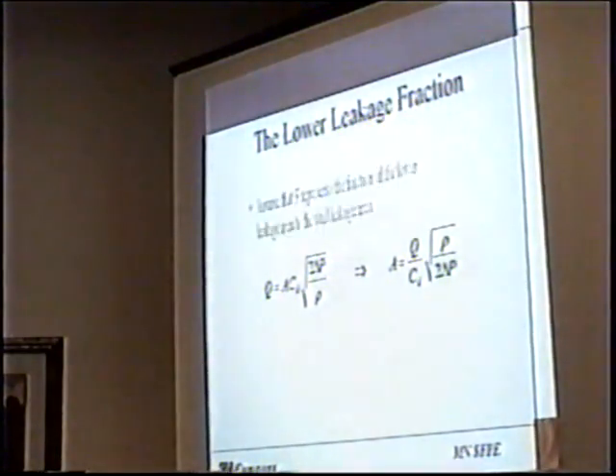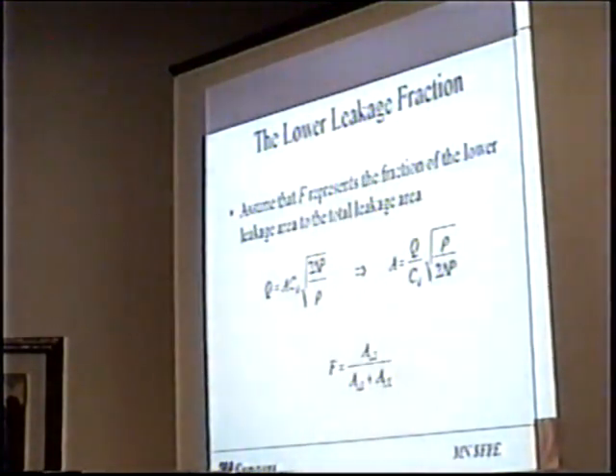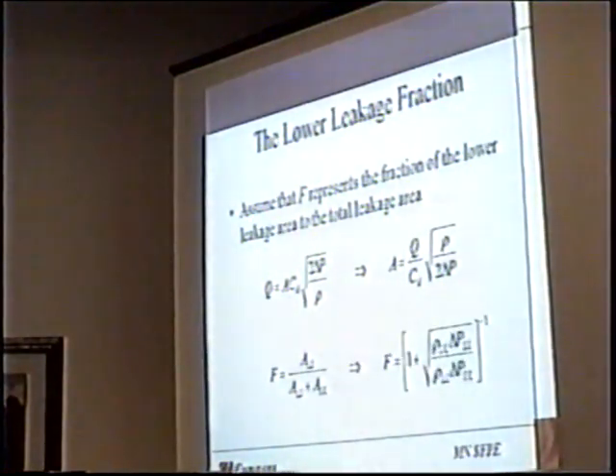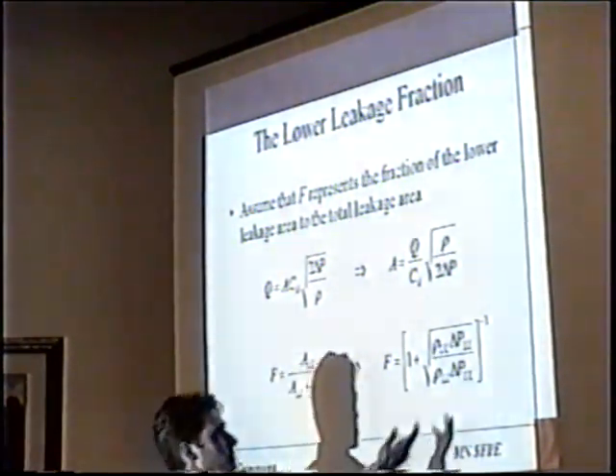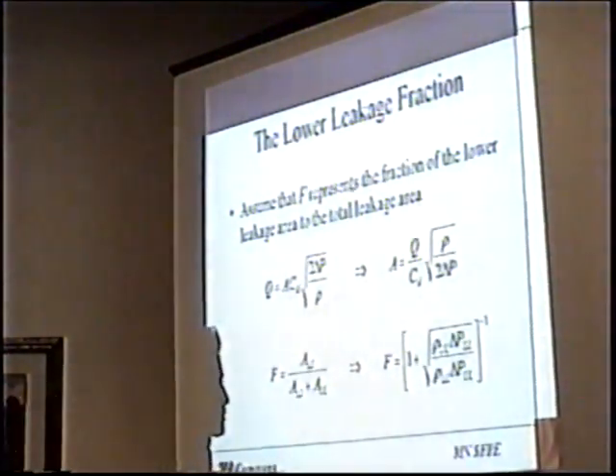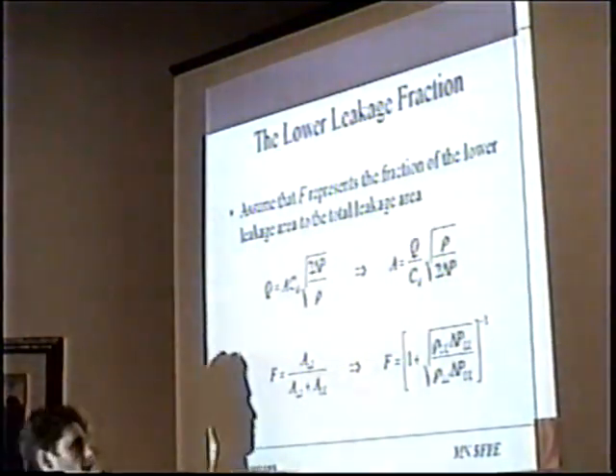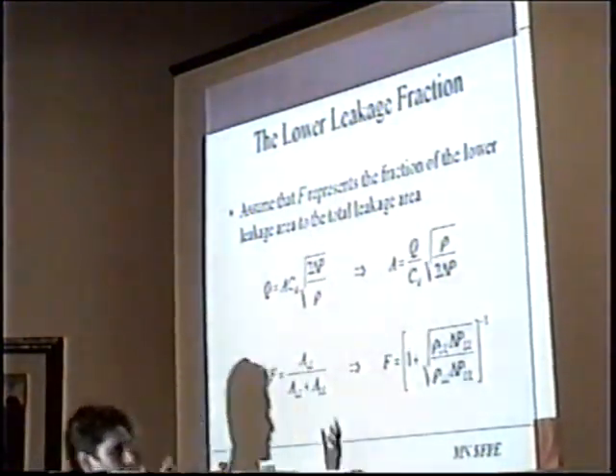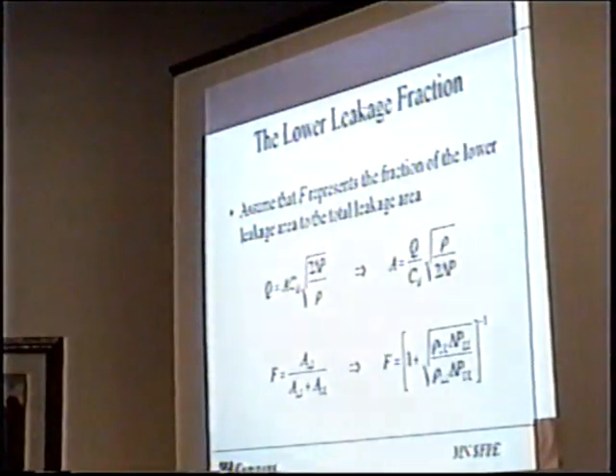Then we'll take our definition that we introduced for our lower leakage fraction F, and plug in the upper right equation for all of the areas. And when we simplify it, we have something right here that we'll be able to use, and I'll show you the results of this. But essentially, all that we're basing this on is two empirical values: the pressure differential at the lower, as well as the pressure differential at the upper, that being on top and below. And also the density of fresh air coming in through the upper versus the mixture density of ambient air and the agent going through the lower.